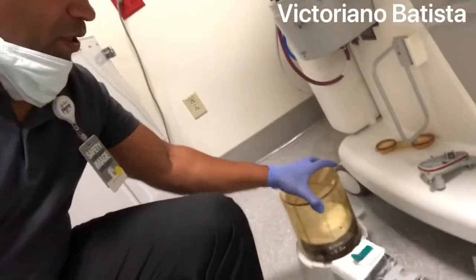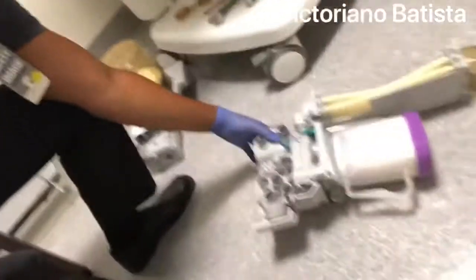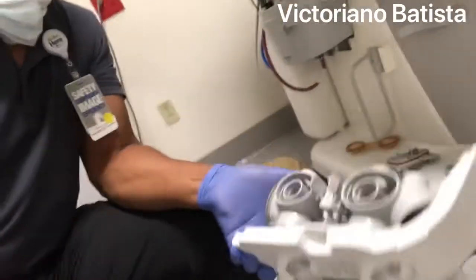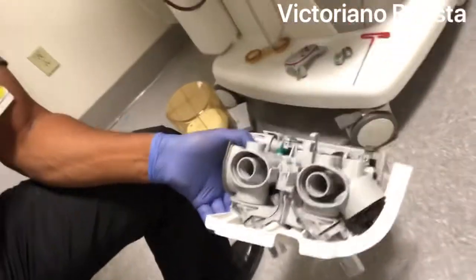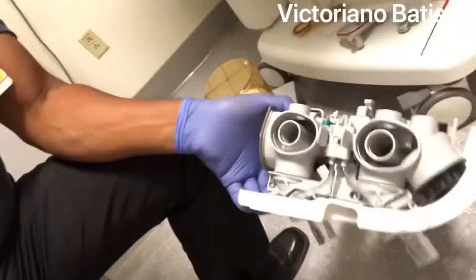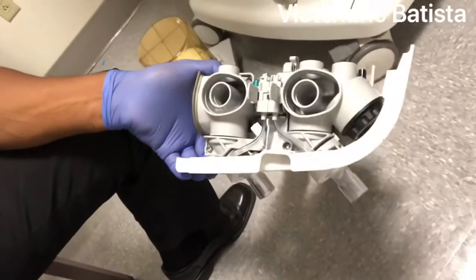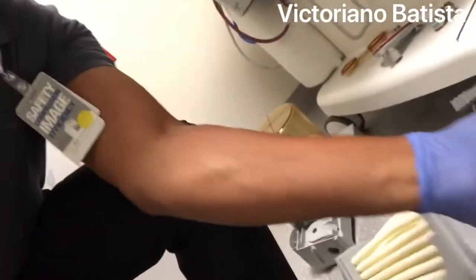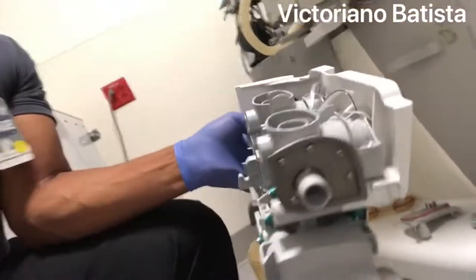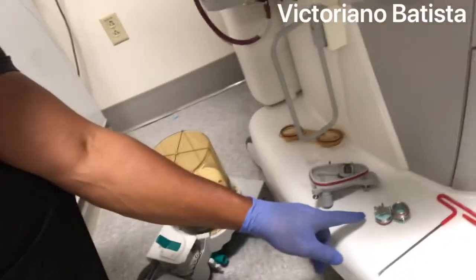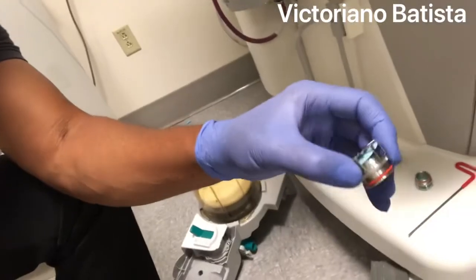And I took this one apart and I have it here separated just so that you can get an idea. This is where the flow sensors go on the unit, and also the exhalation valves. This is the area where I find that it oftentimes gets most neglected when maintenance is being performed, but it also causes quite a bit of problems if the breathing system here is not cleaned out. And I'll just show you these components here that get pretty dirty and need to be cleaned out.